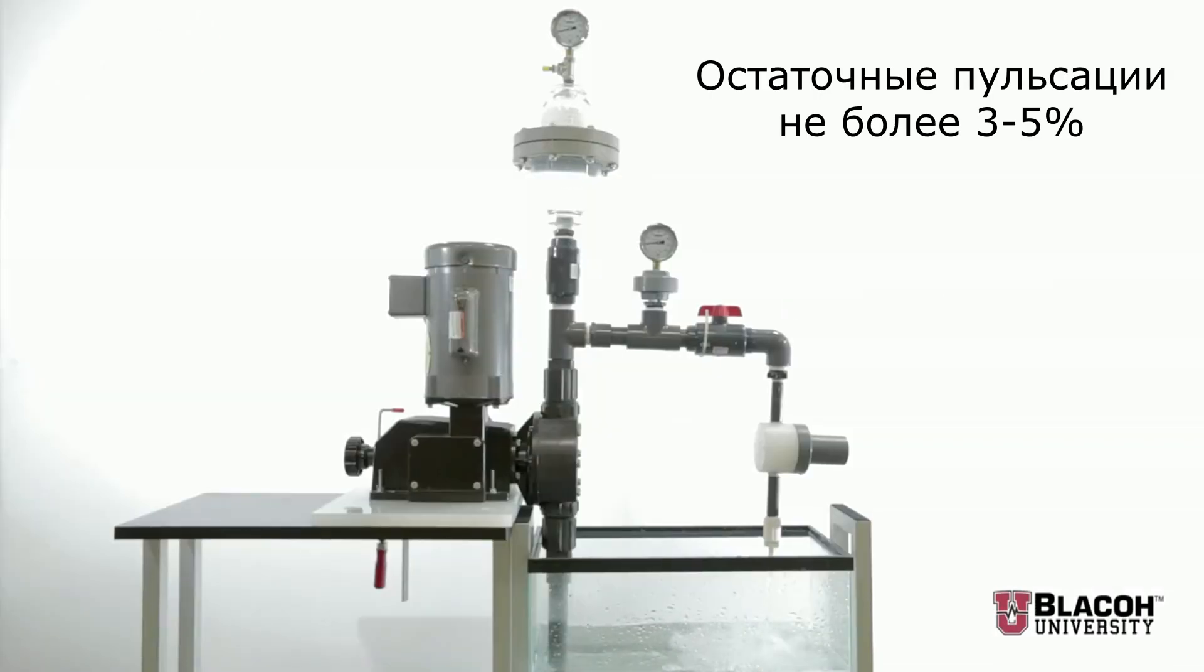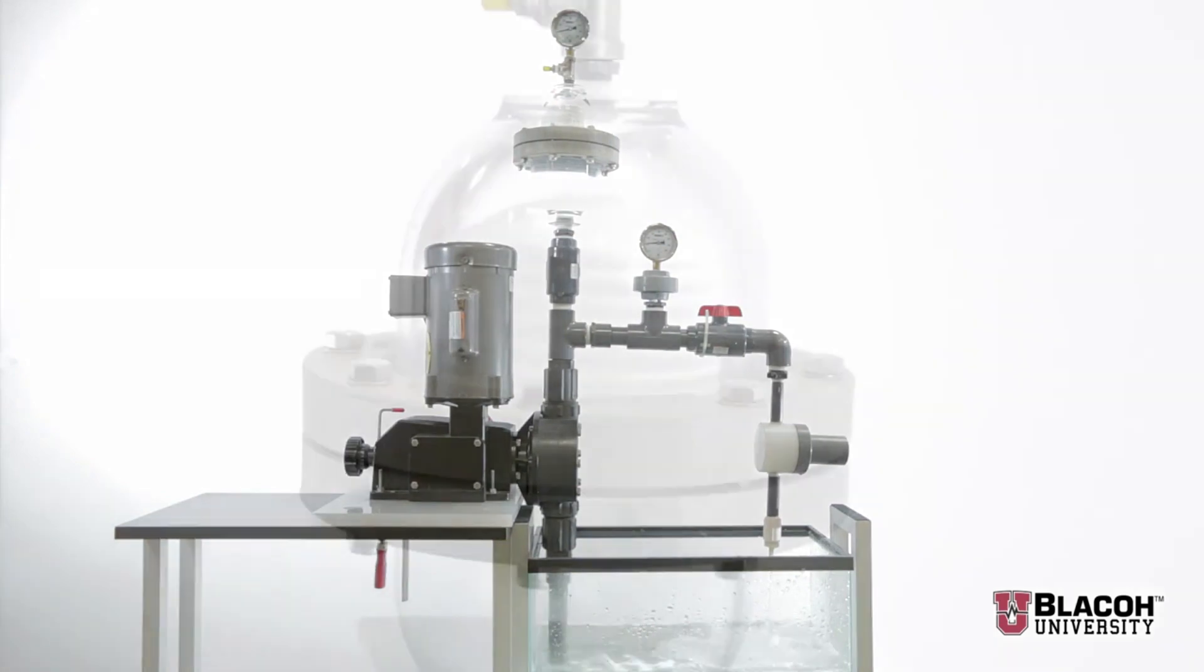With the benefit of the pulsation dampener, the pump only has to overcome 20 psi to continue to discharge liquid, not the 50 psi created without the dampener.